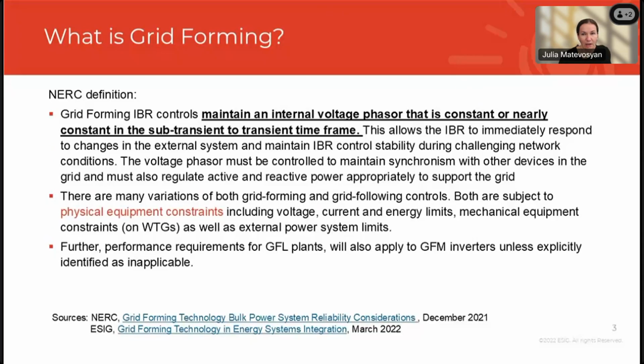All right. So first of all, grid forming definition. I picked the NERC definition, and that's the one that we've been using at ESIG as well, and in the previous webinar. So grid forming IBR controls maintain an internal voltage phasor that is constant or nearly constant in the subtransient time frame. This allows the inverter-based resource to immediately respond to changes in the external system and maintain IBR control stability during challenging network conditions. The voltage phasor must be controlled to maintain synchronism with other devices in the grid, and must also regulate active and reactive power appropriately to support the grid.